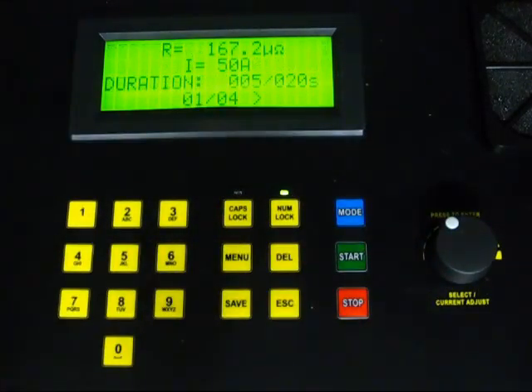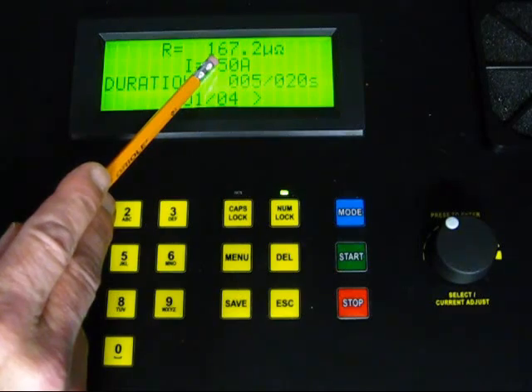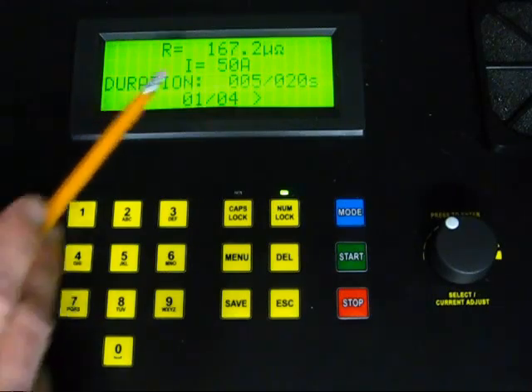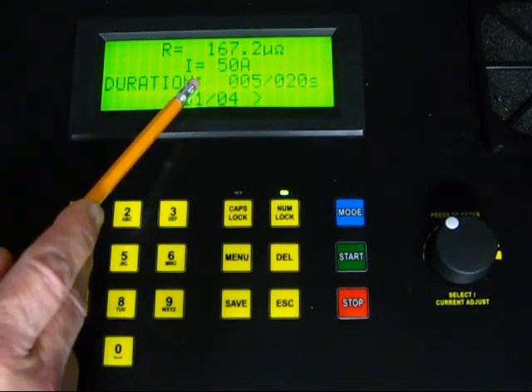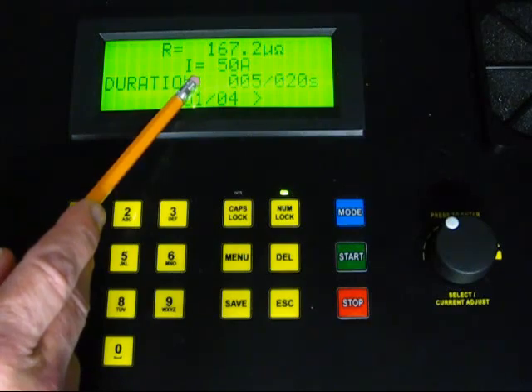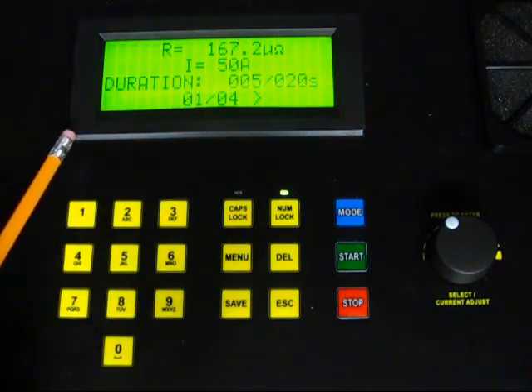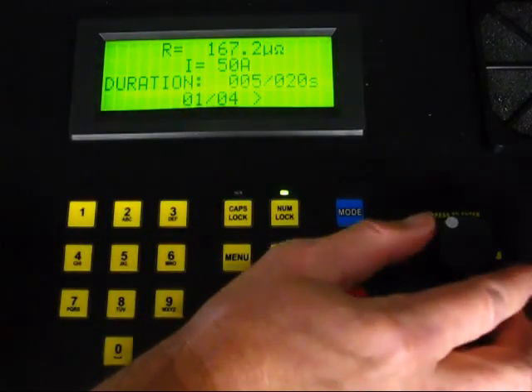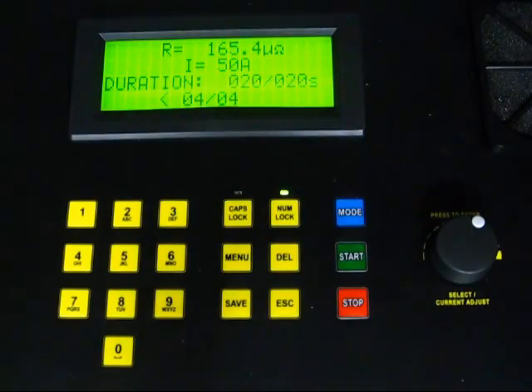The stored test result shows on the top line the resistance measurement at the 5 second point in the test, which in this case is 167.2 micro-ohms. The second line shows the test current, which we set earlier at 50 amps. The third line shows the test duration — the test result was obtained at the 5 second mark within a 20 second test. The bottom line shows that this is the first of 4 measurements stored within this test. To see the remaining measurements, turn the rotary knob to step through the test results. The final result is shown as 165.4 micro-ohms at the 20 second mark.